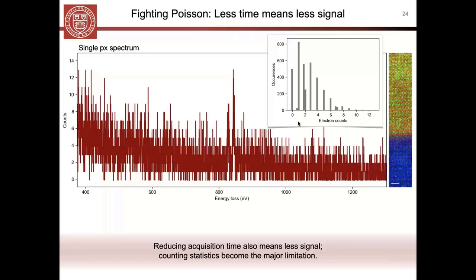If your counts are on the order of 1,000 or 10,000, you have noise, but it's a Gaussian distribution. Here, because we're so signal limited by how fast we have to run our experiment, we're sitting instead in a Poisson regime. So when you're down here, the comparison between your noise, root n, and your signal n becomes very comparable when n is on the order of four.